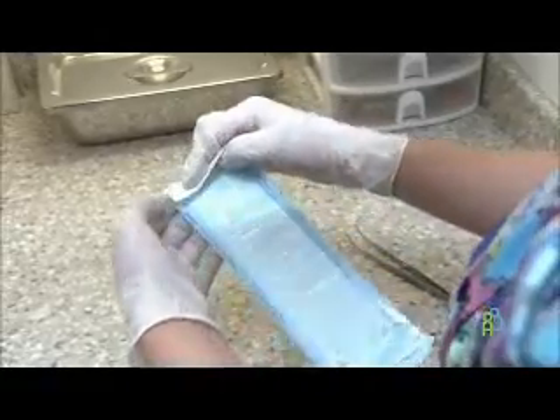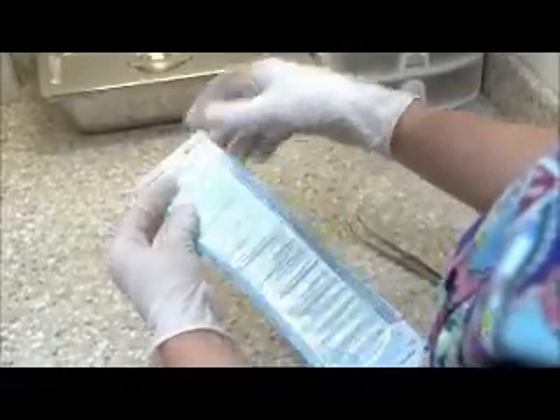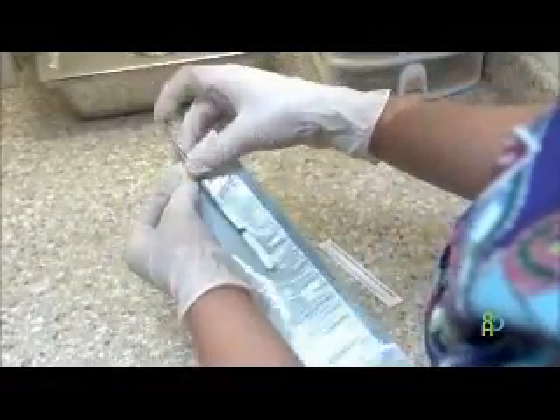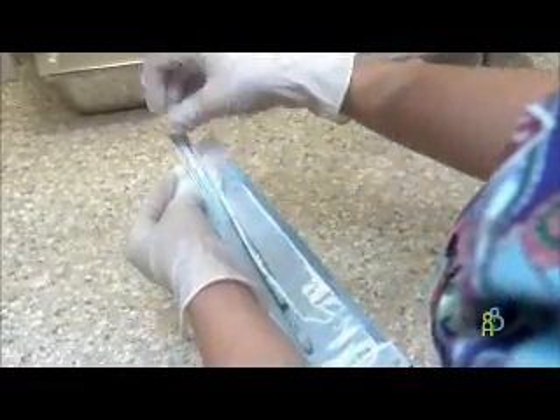The manufacturer's instructions for the use of non-woven wrap should indicate whether single or double wrap is required and must follow the recommendation of the Canadian Standards Association. If there is no validated information which supports the use of a single layer, packages must be wrapped using 2 layers. The layers may be wrapped sequentially or consecutively. Regardless of the type of package used, there are certain requirements that must be in place for all sterile packages.